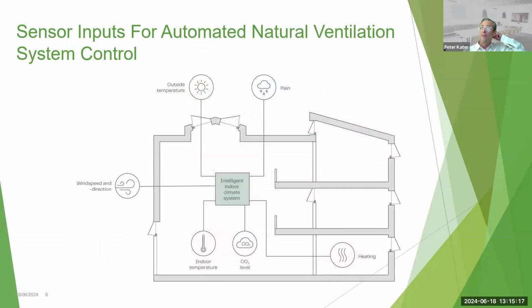The types of sensors that you'll typically need for this type of system, and these all connect into the control system for the natural ventilation actuators. These include, as I said, wind speed and direction sensing, rain, outdoor temperature, indoor temperature and relative humidity, and also the indoor CO2 level. That's an important one, particularly for meeting rooms and classrooms and so forth. And then a link with the mechanical heating system to provide information telling it what to do and when.